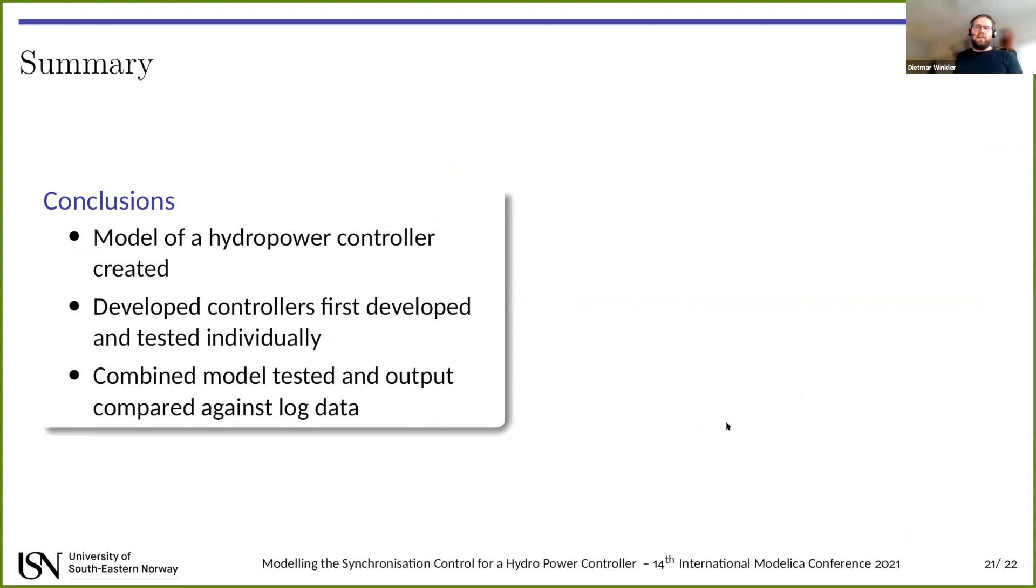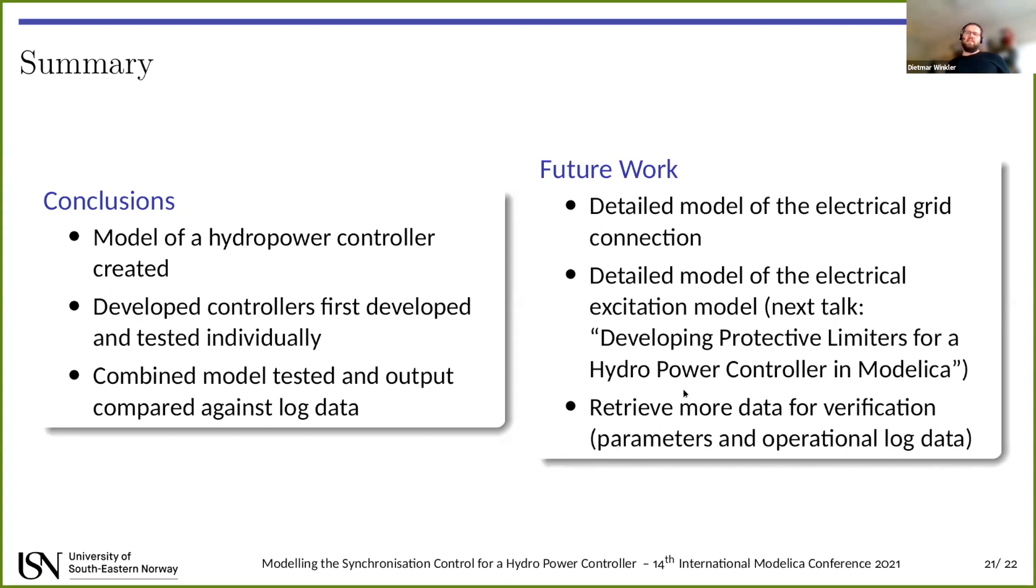This concludes my presentation. The model of the hydropower controller was created. The different controls were first implemented individually and also tested individually and then combined and tested against log data. You haven't seen any log data here. The reason is basically I wasn't sure what I'm allowed to show and what not. So I rather took the easy way out and didn't show that verification log data, but our partner was actually satisfied with the result. Future work is the detailed model of the electric grid because you could see there was very little in those terms. Our partner in this case was not so interested because a small power manufacturer or producer doesn't have any restrictions as to what the voltage regulation is. So they didn't have any data on that part, but we're now working on different projects where we're including also more detailed models.